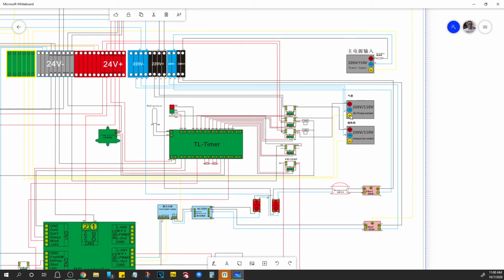And then you can check it at the filters. You can check for AC power here on L1 and N1. And if you have it here, you can check it here. If you don't get it there, then you know that this filter's bad. Then check it at both sides. You just have to go through with your meter and hit these test points and see if you're getting 110.